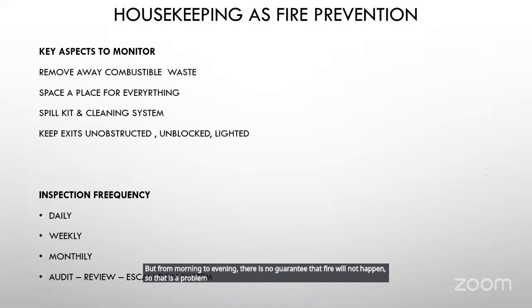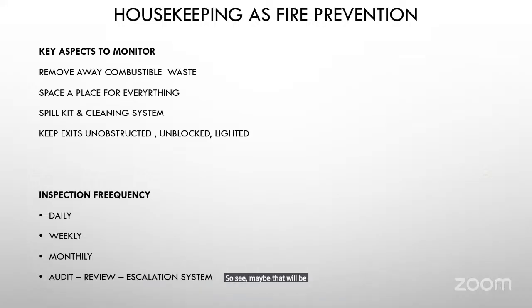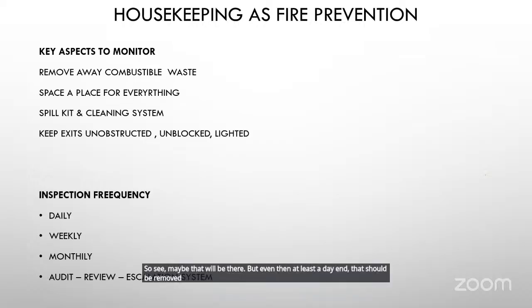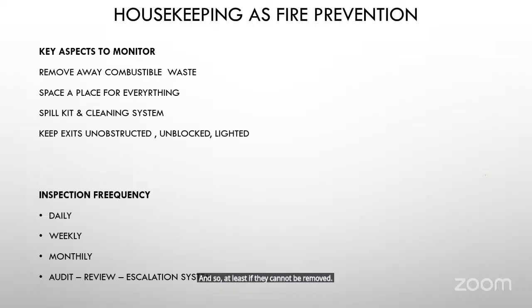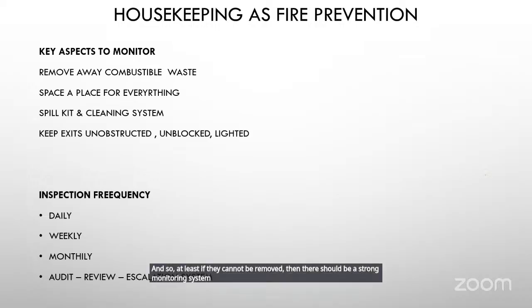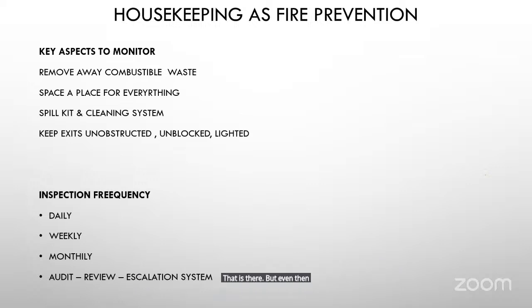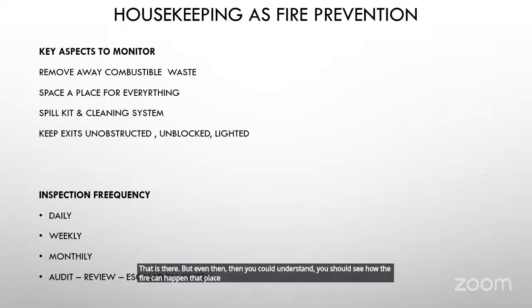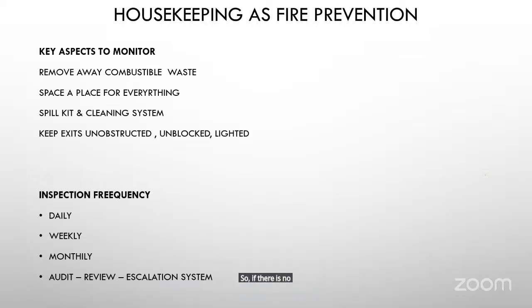So maybe that will be there, but even then, at least at day end it should be removed. And if it cannot be removed, then a strong monitoring system and a strong protection and prevention system should be there. If combustible items cannot be removed immediately, and practically speaking, every day you cannot remove everything, even then you should see how fire can happen at that place. If there are no ignition sources, then your risk is over. 50% of the risk is over.